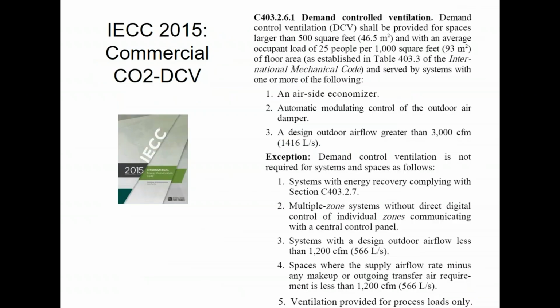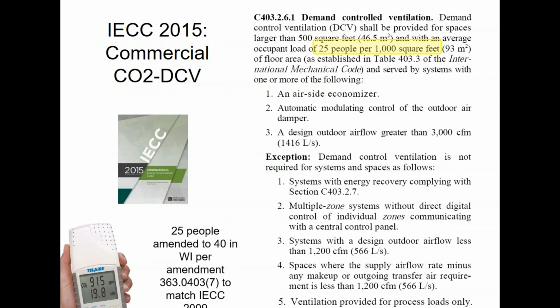Demand control ventilation is frequently required by code as well. In Illinois, if the space has a people density of 25 people per 1,000 square feet or greater, and in Wisconsin, if it's 40 people per 1,000 square feet or greater, then you're going to need to consider demand control ventilation, where we use a CO2 sensor to monitor the breathing activity of the building occupants. The more breathing activity, the more people, and hence the higher the ventilation we need. Or more importantly, the fewer people, the lower the ventilation air we can go down to. So this is when that code would kick in.